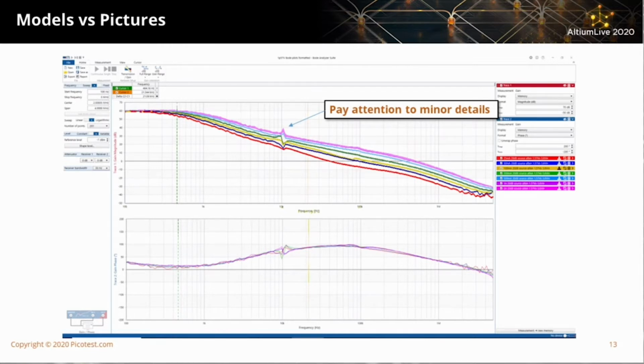So we got a giant current probe, one of those Tektronix current guns that looks like a pistol. And we put it on the battery cable, and sure enough, 200 amp sine wave, the battery cable was oscillating at about 200 amps at 4 kilohertz. How does that happen? You know, the company that I did this effort for was meticulous about their modeling, and they modeled every single box in this entire satellite. And so they questioned how it is that they possibly could end up with a scenario like this, where they had an unstable battery bus and didn't know it.